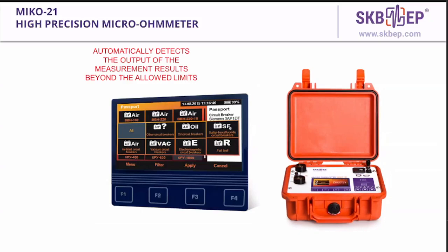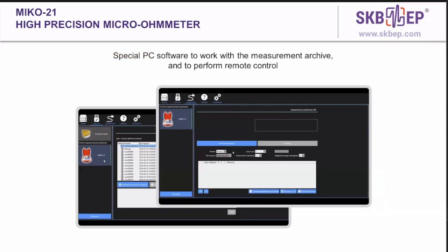The archive of the instrument contains nominal values of circuit breakers with indication of maximum and minimum permissible contact resistances. As a result, the device indicates if results of measurements go beyond the permissible limits. We integrated the basic archive, so you can use it, or you can extend it, introducing your own data into the archive. We can transfer the data to a PC. We can also perform measurements by connecting the device to the PC with the cable and the software, of course.